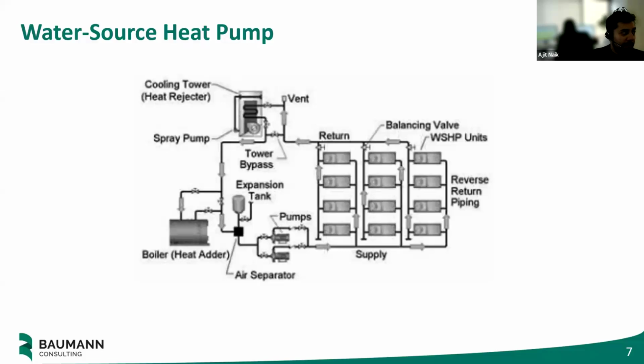So this led folks to come up with the idea of water source heat pumps, right? You can see on the right, you have a bunch of little heat pumps, say, for example, in hotel rooms or in apartments in a multifamily building. And all of those heat pumps, instead of extracting their heat or cooling energy from the outside air, they're piped, right? They get a stream of neutral temperature water, right around 50 degrees, that can act perfectly as a heat sink or a heat source all year round. So maybe some of these units are extracting heat, maybe some are rejecting heat and cooling, and they can all share that energy and have this common loop of always neutral temperature energy.